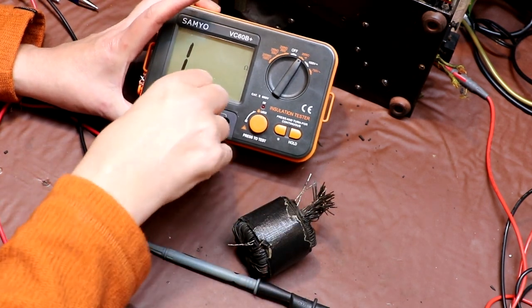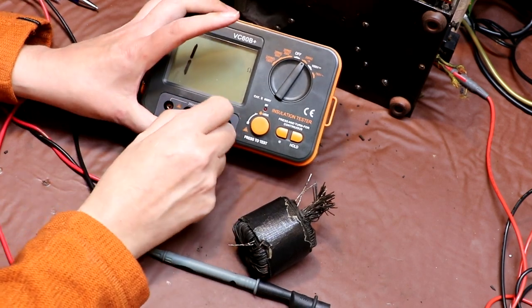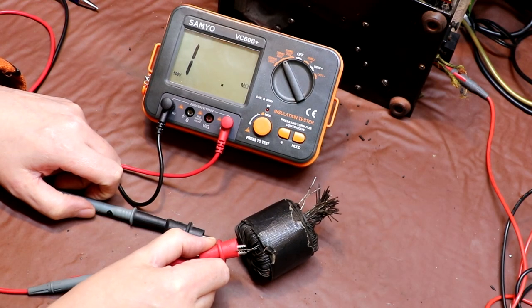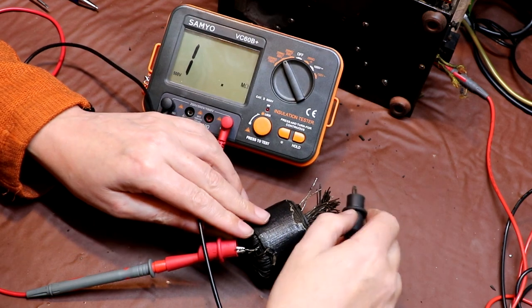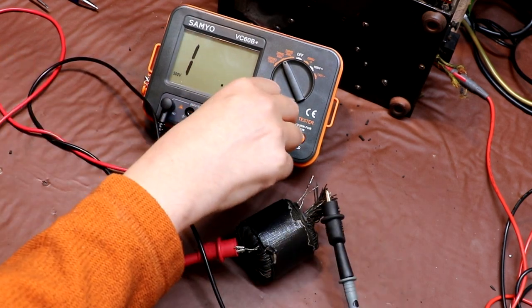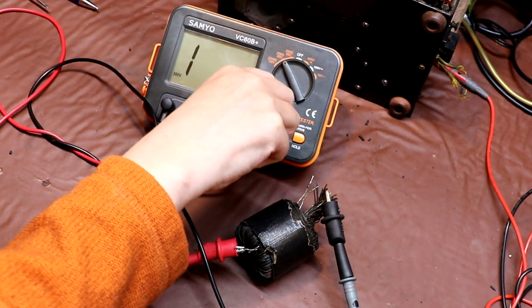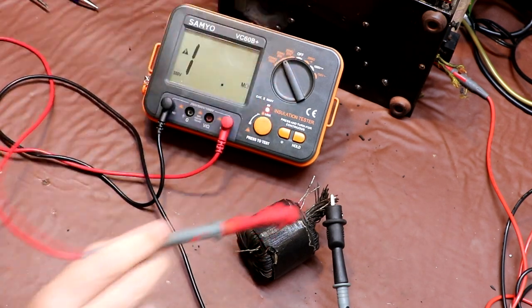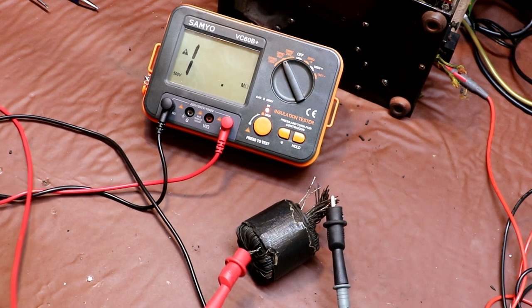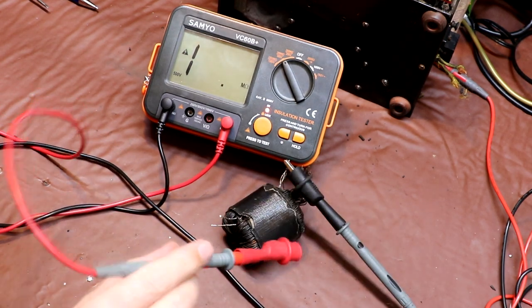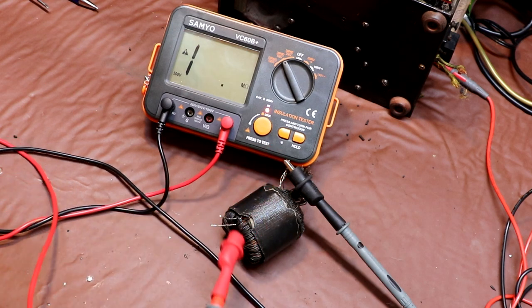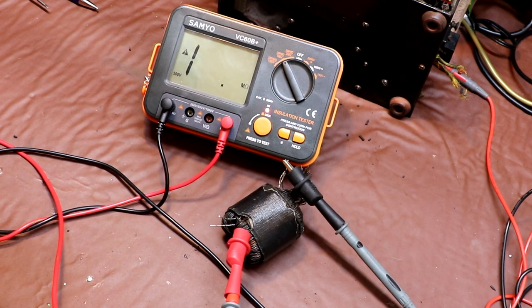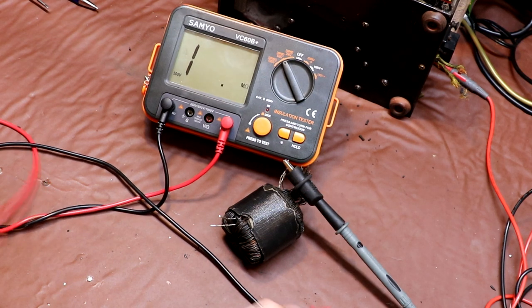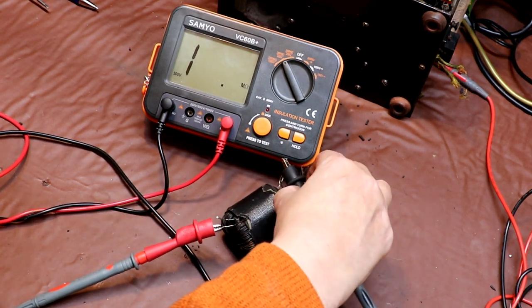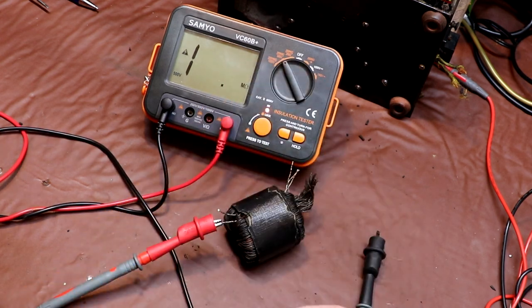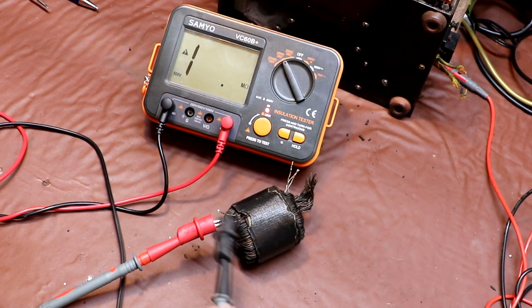Let's switch our meter leads round and then we will do some high voltage insulation resistance checks. So let's put one clip on the secondary there, and we'll put another clip on the primary and do our test. I think that's coming up clear. Let me just test our meter. Yeah, that's okay, so let's double check that again. Let's also check we haven't got a short circuit between our primary winding and these core windings. So that looks okay. And let's do the same for our secondary windings. So that looks okay.